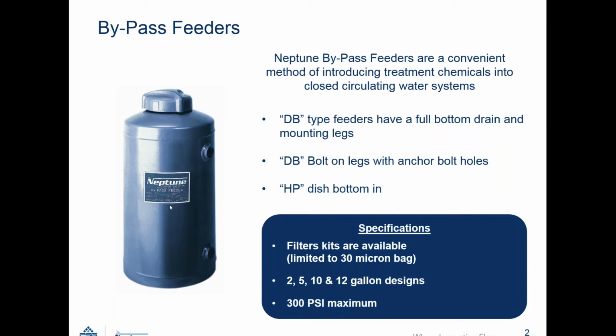We have the DB types, which have a bottom drain and also have mounting legs. The mounting legs can be anchored to the floor, where the HP models are a dish bottom, mounted to the floor. These particular feeders also have optional filter kits. They are limited to 30 micron bags because these are designed generally to feed chemicals, but there are instances where filters can be used or are required. And while they're in the system, we can have these available if needed. But again, they are limited to 30 micron bag sizes.